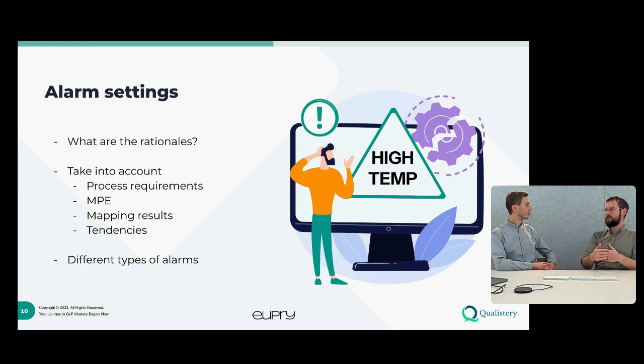So first of all, how risk hungry are you? Having some sort of early warning alarms in place is a great place to start. That's the practicalities, but also, what are your rationales for choosing those? There are several things you need to take into account when setting these alarm settings. First of all, the process requirements. What are the requirements from that process? Is it very critical that you store it between exactly 2 and exactly 8 degrees, or how much deviation can we handle?